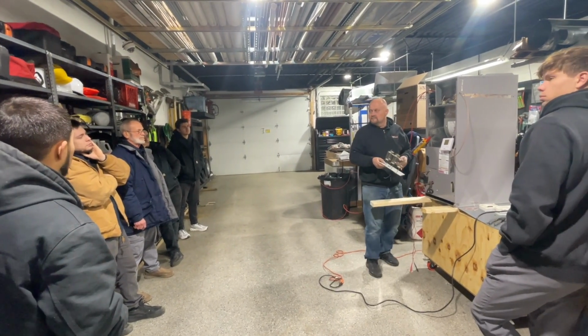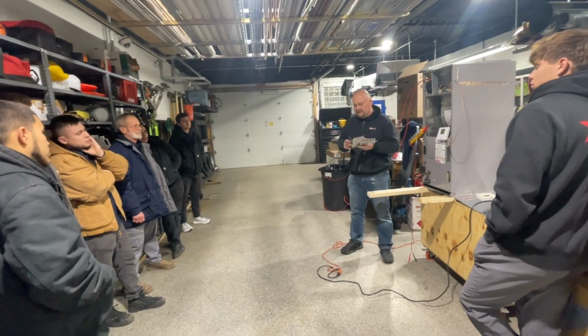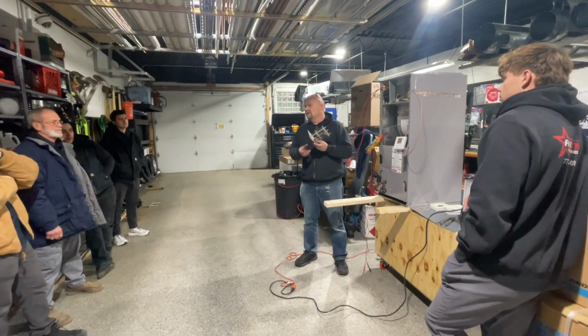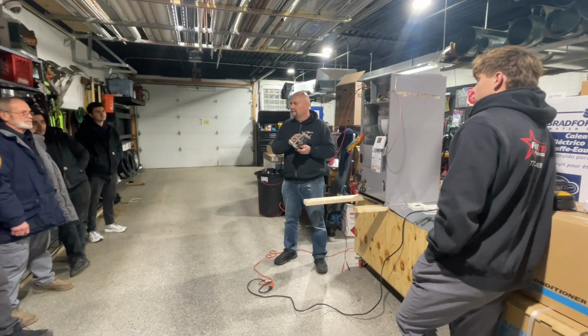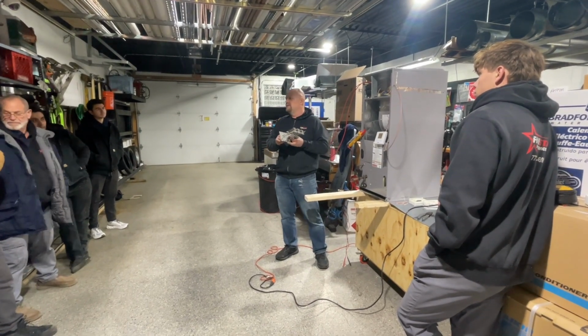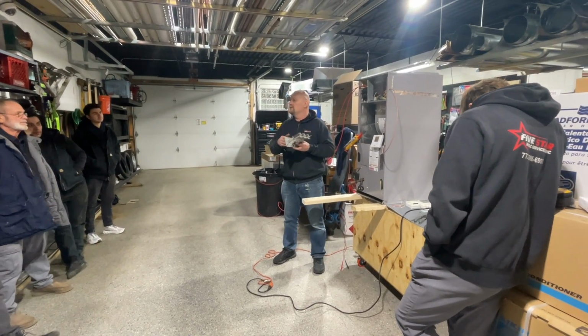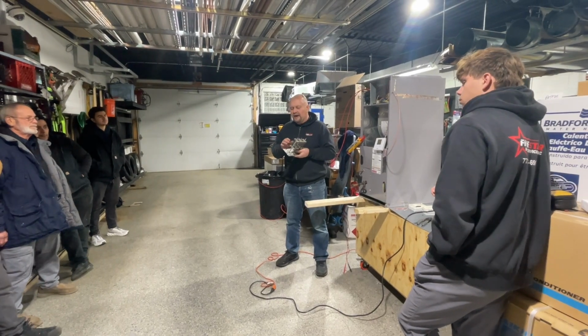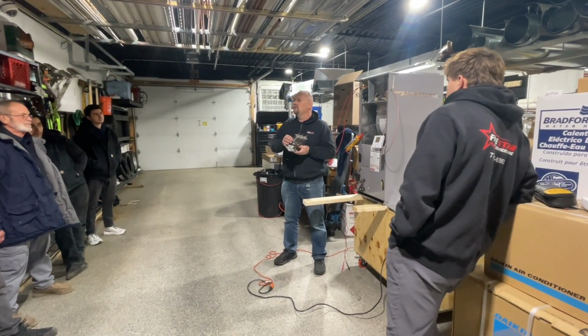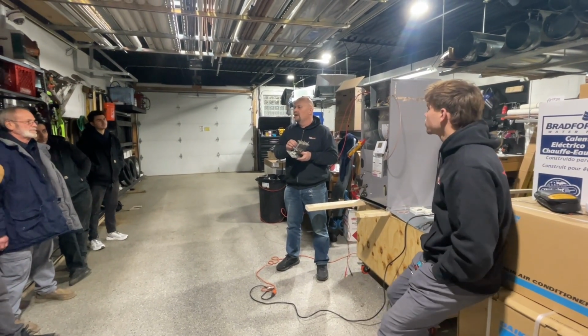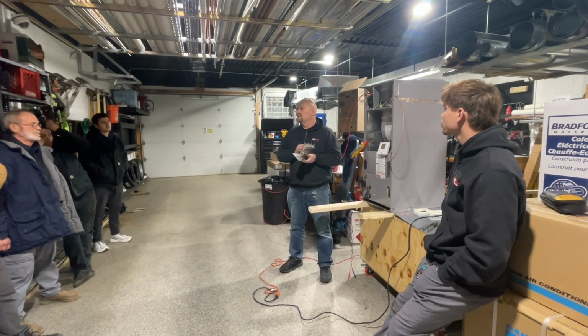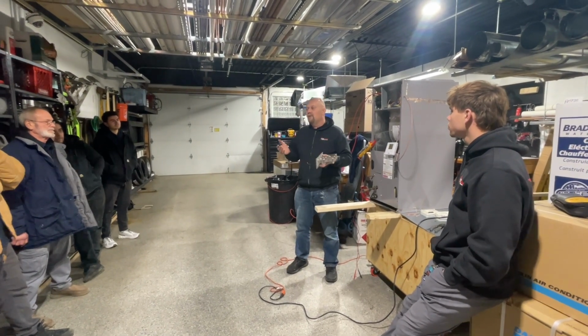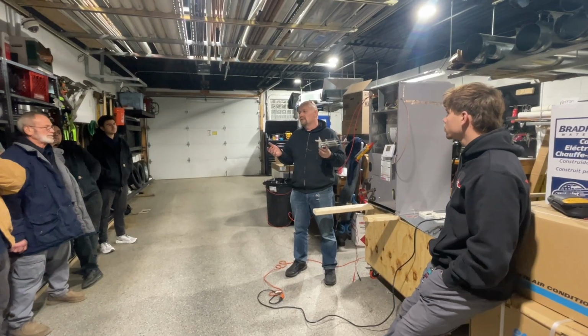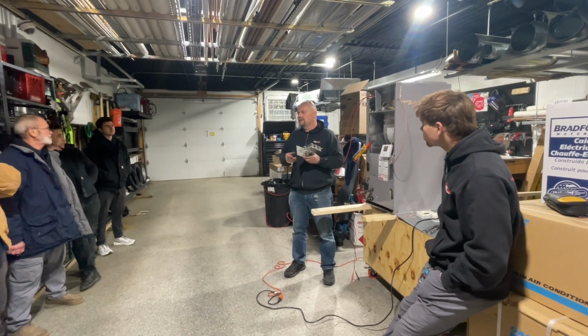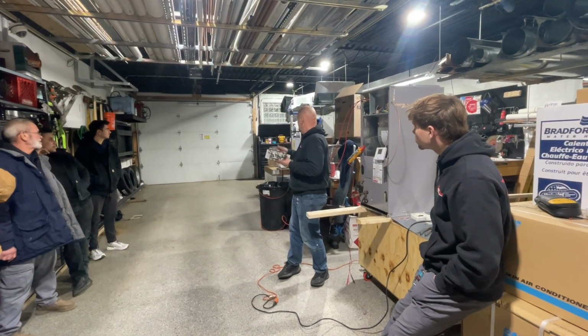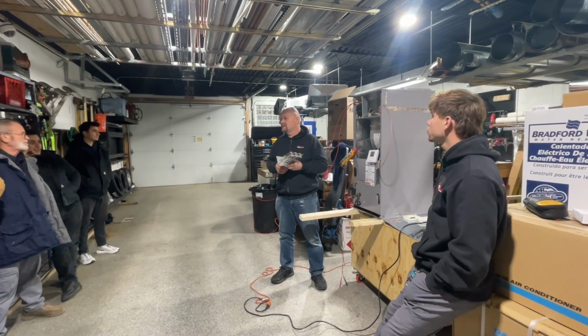The wires burn too. Typically these wires will surrender first. This is supposed to be a little bit thicker, and this is supposed to surrender. It's supposed to burn before this burns, right? But with ultimately being used, cooling and heating of itself, and if it's not getting enough airflow, this will also burn through. At any point, electric heating is somewhat dangerous, so you've got to make sure everything is nice and tight. You've got to make sure everything is well connected.